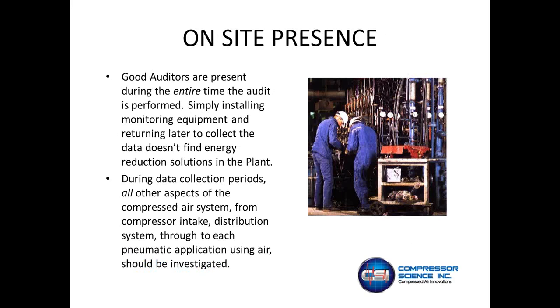Again, on-site presence means that if you're auditing a compressed air system, you should be present looking at the compressed air system from intake to point of use, how they're using compressed air. A lot of companies come in and put in the black box study, they hook the amp meters to the compressors, they put a pressure transmitter in, and they come back a week later and download the data without really any correlation to what's going on in the facility, how that's impacting the compressed air system demand.